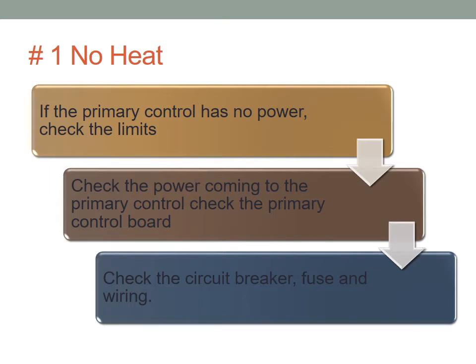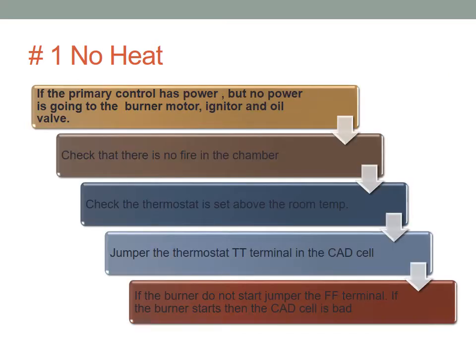So make sure it's 120 volts. Check the switches are made. Okay, so we'll check the power coming in is 120, and we want it to be 120. Check the circuit breakers and fuse and make sure they have continuity. I always keep saying check continuity because it's always an important thing to check when you have no power and no nothing. Okay, no heat.